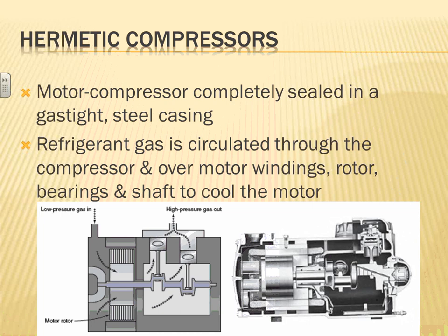And when I teach electricity, I always say the enemy number one of an electrical system is heat. If you can remove heat, you can make a number 14 conductor carry 30 amps, if you don't care about smoking the conductor or burning it, or if you can remove the heat. So if you can remove the heat out of this motor, you can abuse this motor and make it work harder. And by having the refrigerant go over the bearing as well as over the winding and so forth, in this combination, they make this motor work much harder than any other motor.